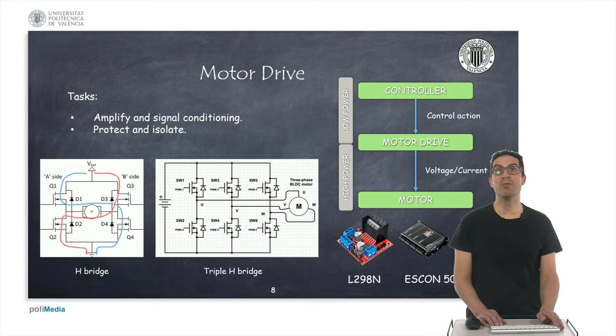The motor drive is a very important element for controlling a motor. It is in charge of supplying the energy in the form of voltage and indirectly current that the motor needs, but isolating the low power signals at which the controller usually works from high power signals at which the motor usually requires. Therefore, one of its main tasks consists of properly amplifying and conditioning the signals to the motor, also protecting the motor from high-voltage spikes that could damage it and electrically isolating the controller from the motor drive.